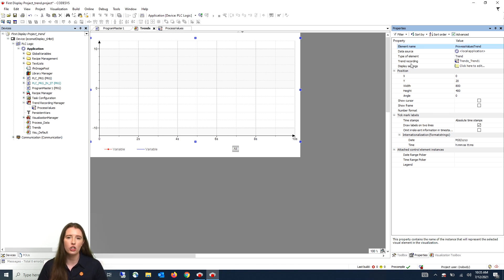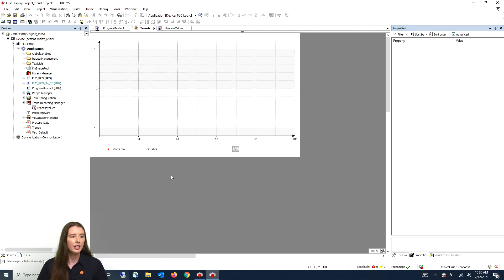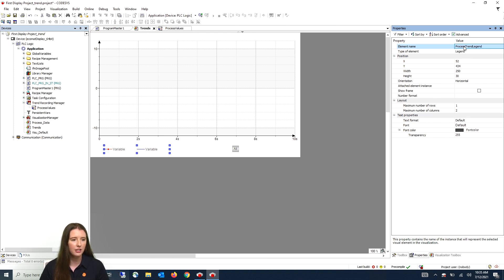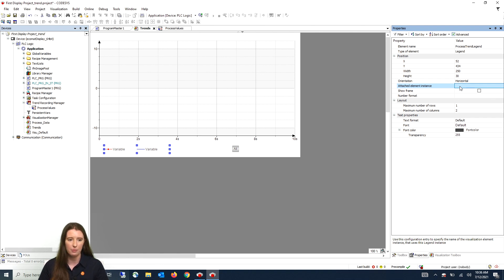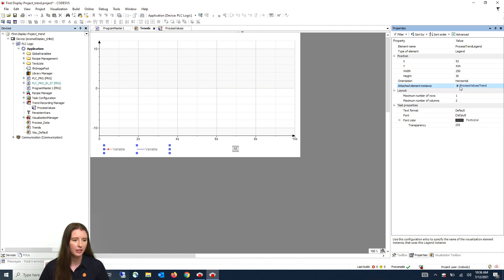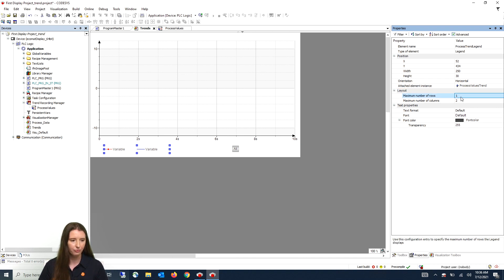You will then go to where it says trend recording, drop down the window, and select process values — which is the name of the trend recording we created earlier. Next click on the legend element and give it the name process trend legend. Then go to where it says attached element instance and type in the trend element name, which is process values trend. Then change the maximum number of rows to two and the maximum number of columns to one.